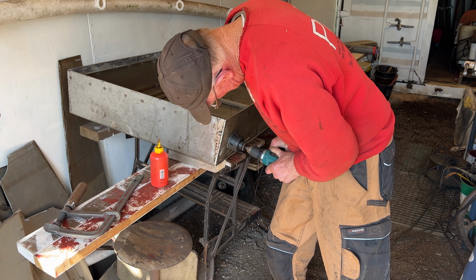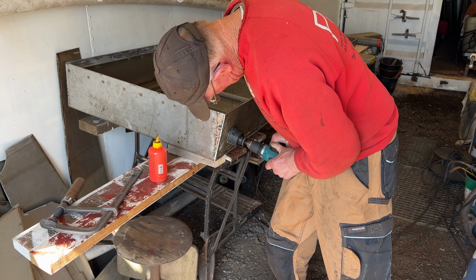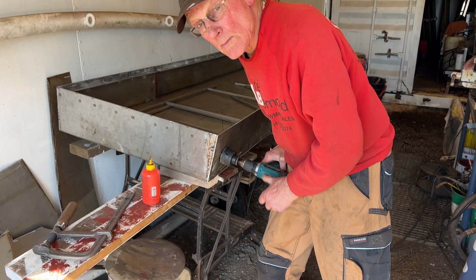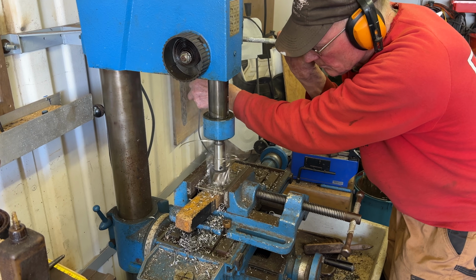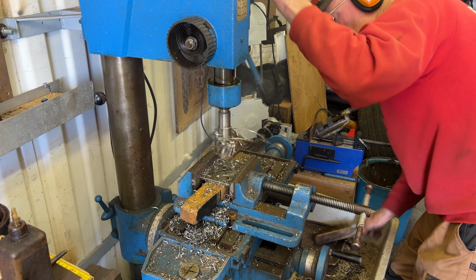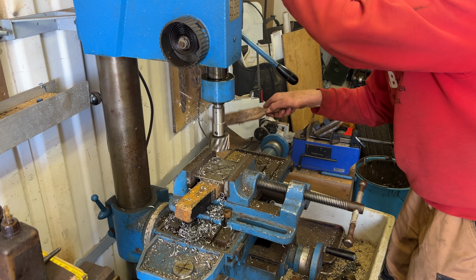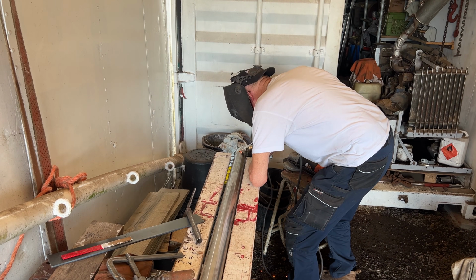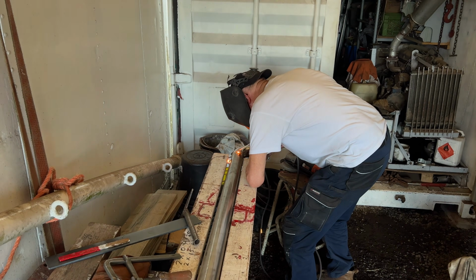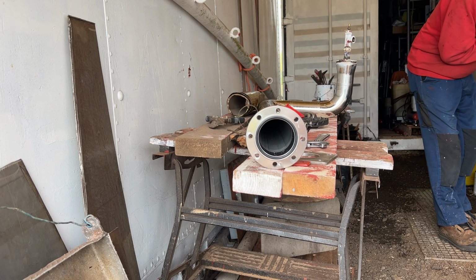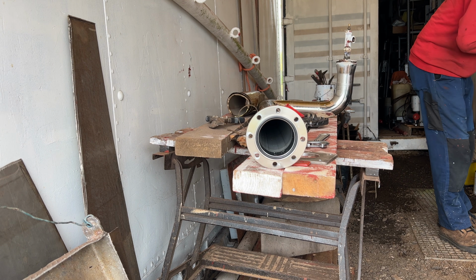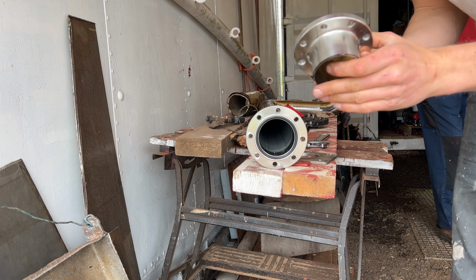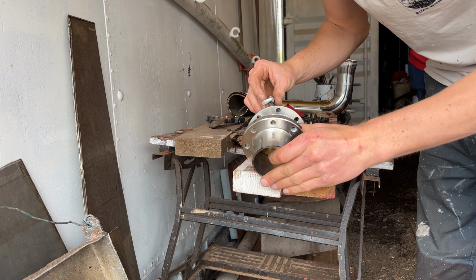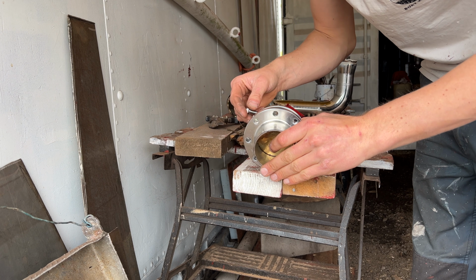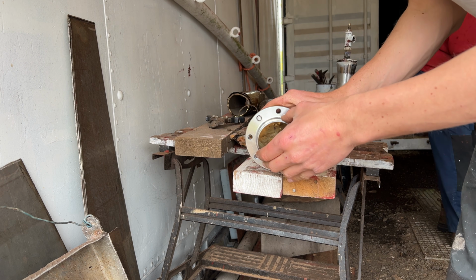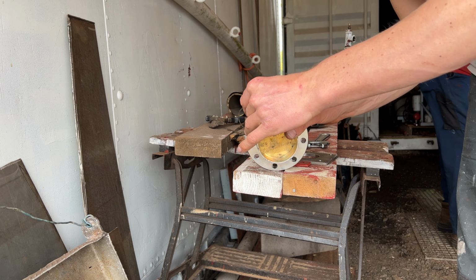And of course, a battery fire inside a sealed box means overpressure and toxic gases, especially once you start adding water. So we need a ventilation pipe that channels hot gases to the outside of the ship. But then if we leave that open, it compromises our water and air tightness. So we're installing a rupture membrane in the ventilation pipe that is able to stay closed during normal use and air expansion, but in case of overpressure due to fire and water evaporating, it will break. So we need a rupture pressure of around 0.2 of a bar.